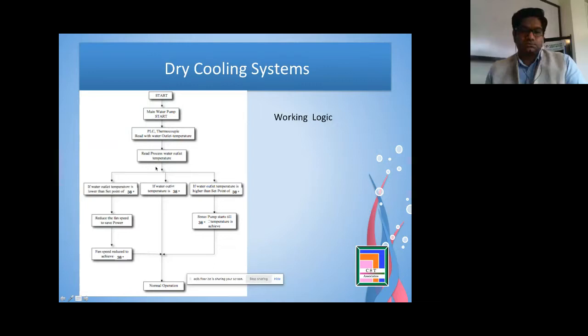Will have three kinds of readings. So let's say our working temperature is 38 degrees, 38 degree temperature is the requirement. If water outlet temperature is lower than the set point of 38 degrees centigrade, what will happen is it will reduce the fan power to save the energy. And once it balances out, where the air requirement versus the surface area matches, and if the water outlet is 38, there is no need for the water spray or to reduce the fan speed also. It means this is where our design dry cooling temperature is there. So this portion is for the dry zone. And this is the adiabatic zone.